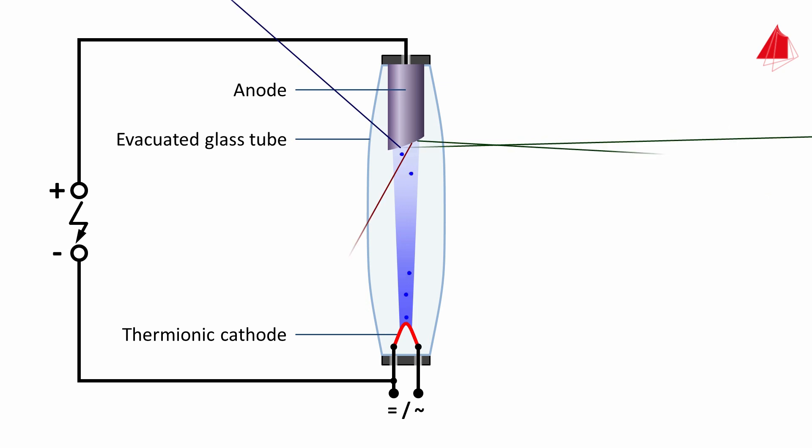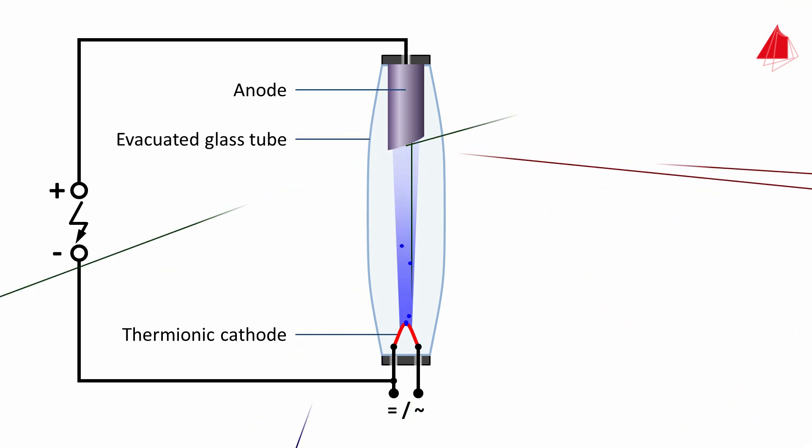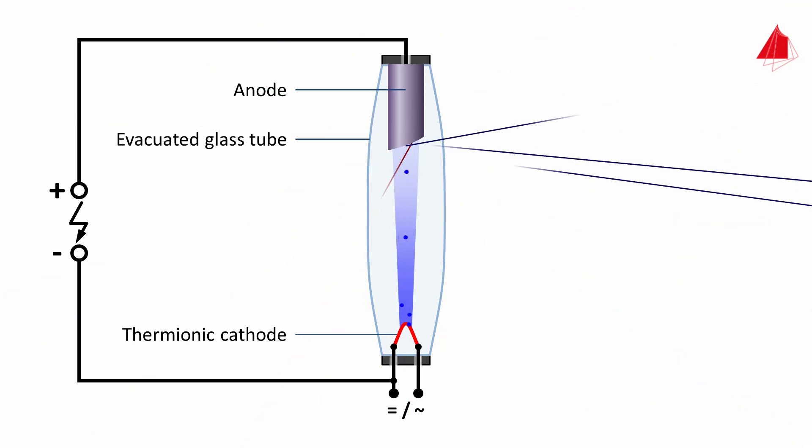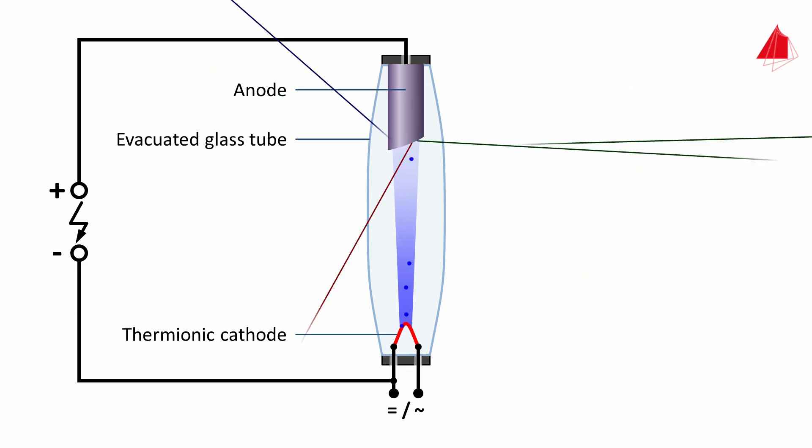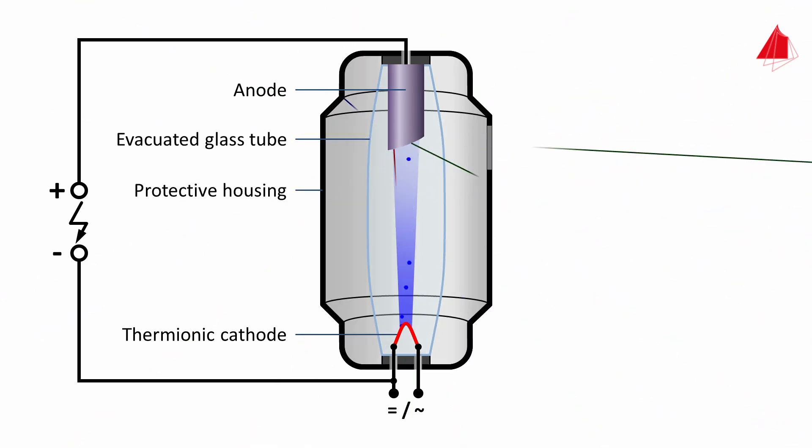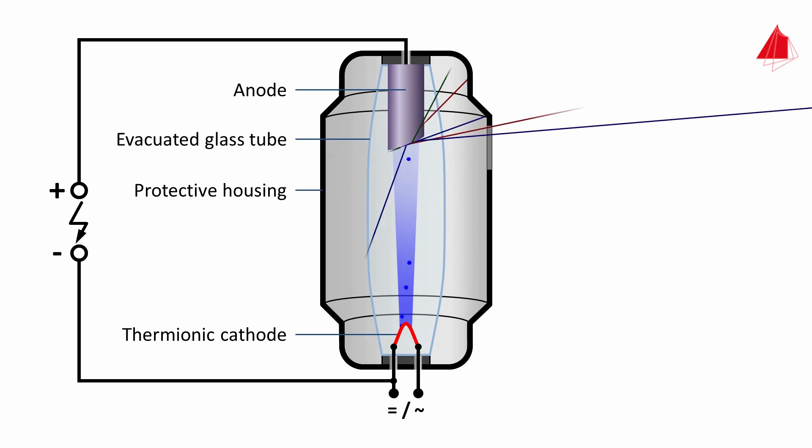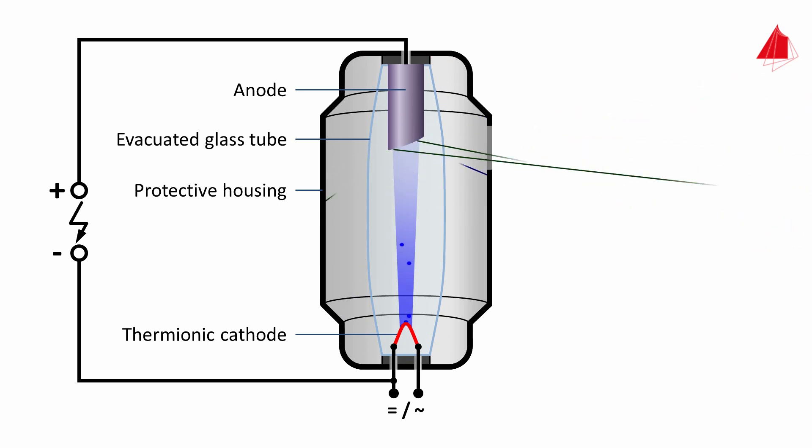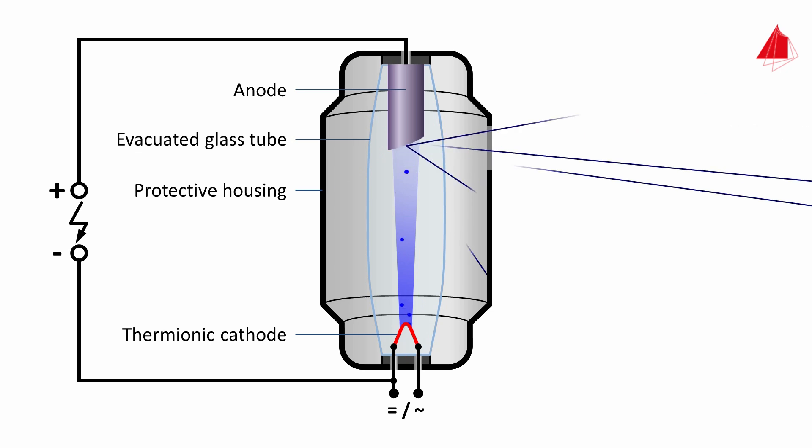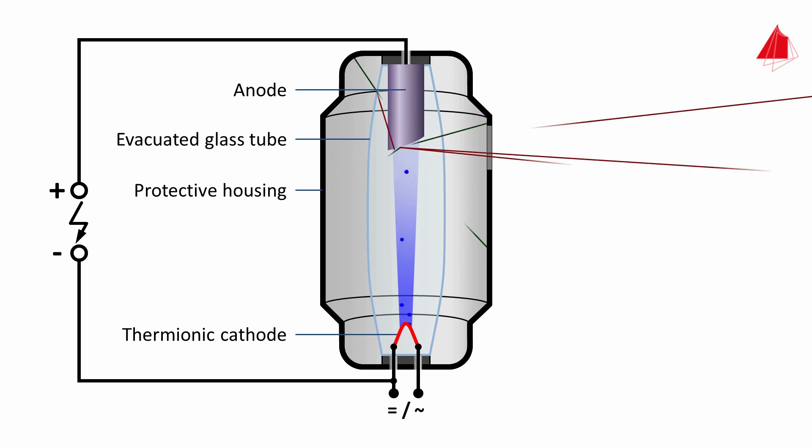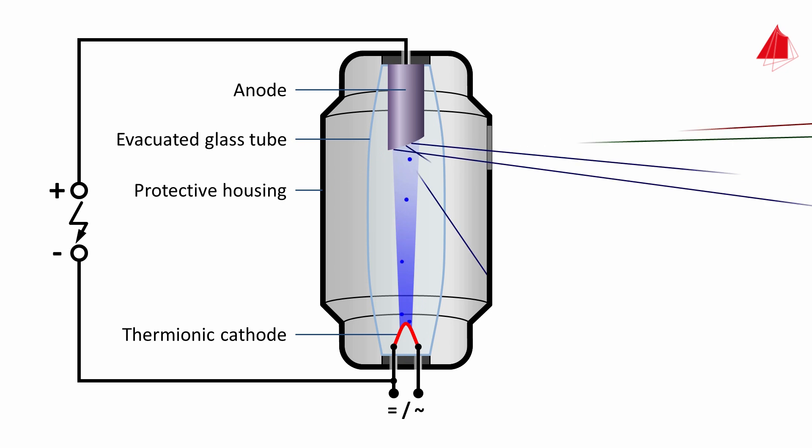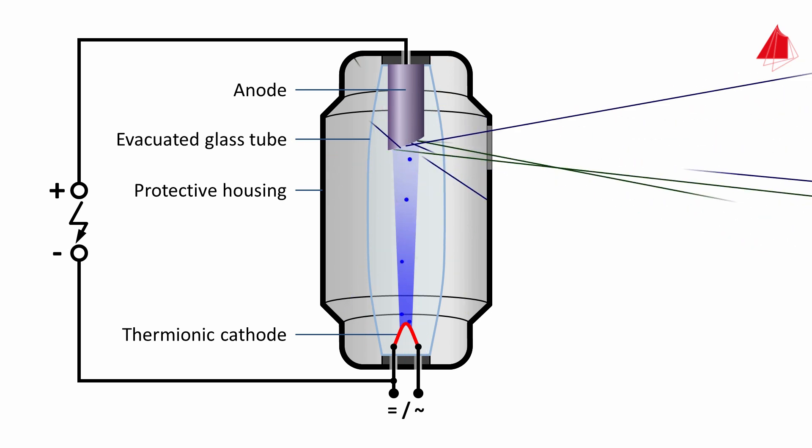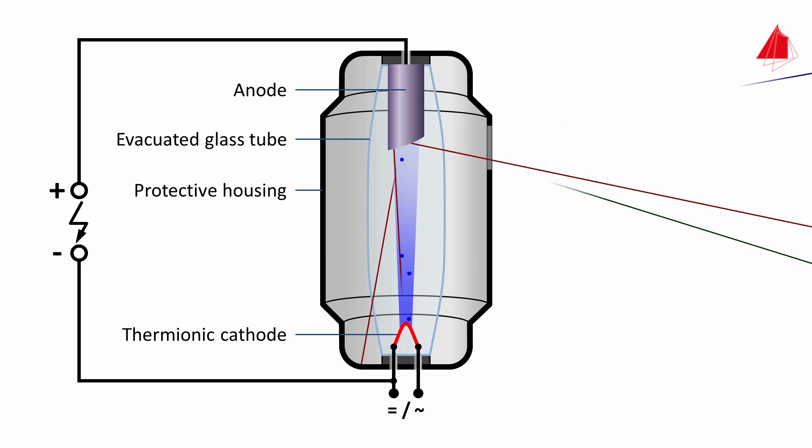Because the anode surface is slightly inclined, the emission of the x-radiation towards the right is more intense. But a certain proportion also radiates in other directions. A protective housing shields x-rays going in unwanted directions. The desired x-radiation can only reach the outside through a small transparent window. With this setup, a high resolution x-ray examination is not yet possible. The problem here is the large area on the anode where x-rays are generated. The x-radiation is too diffuse, so a fuzzy and low contrast x-ray image would be the result.